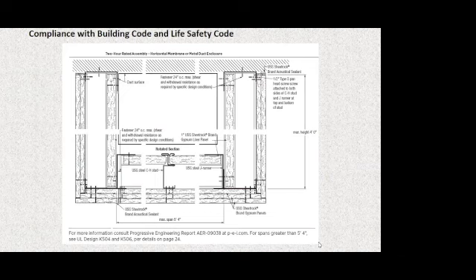But before we do that, let's benchmark how that test specimen compares to what's in the code, because you're not going to find in the code duct A or duct B. They're just going to describe the fire resistance. The test specimen tells you what they tested and whether it meets the fire resistance described in the code. But what the code conventionally, prescriptively describes is a code path back through Chapter 7 to 703.2.1. And depending on the orientation of the assembly that is described as needing to be fire rated, it's going to be either in the horizontal orientation or the vertical orientation.